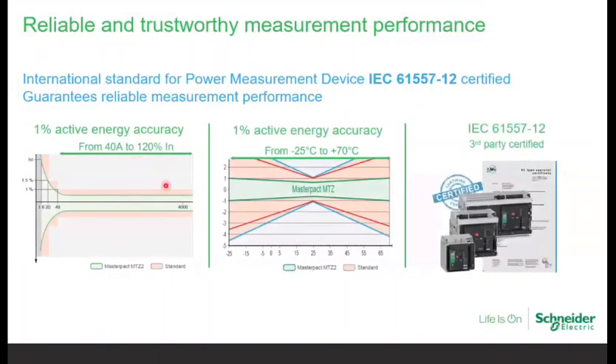So we have a reliable and trustworthy measurement performance. If you take a Masterpact MTZ ACB, this red zone is the zone declared by the standard for any performance measurement device, be it a meter, or the inbuilt metering of an ACB or MCCB. You can see the MTZ ACB is very well within the standard. What is the standard talking about? We have 1% accuracy from 40 ampere to 120% of In. It means if you have a 1000 ampere breaker, from 40 ampere to 1200 ampere, you will get class 1 energy accuracy end to end. The next point, again, the red zone is the standard expectation and the green zone is the MTZ performance. You can see it is very well within the standard, or even better than what the standard is asking.